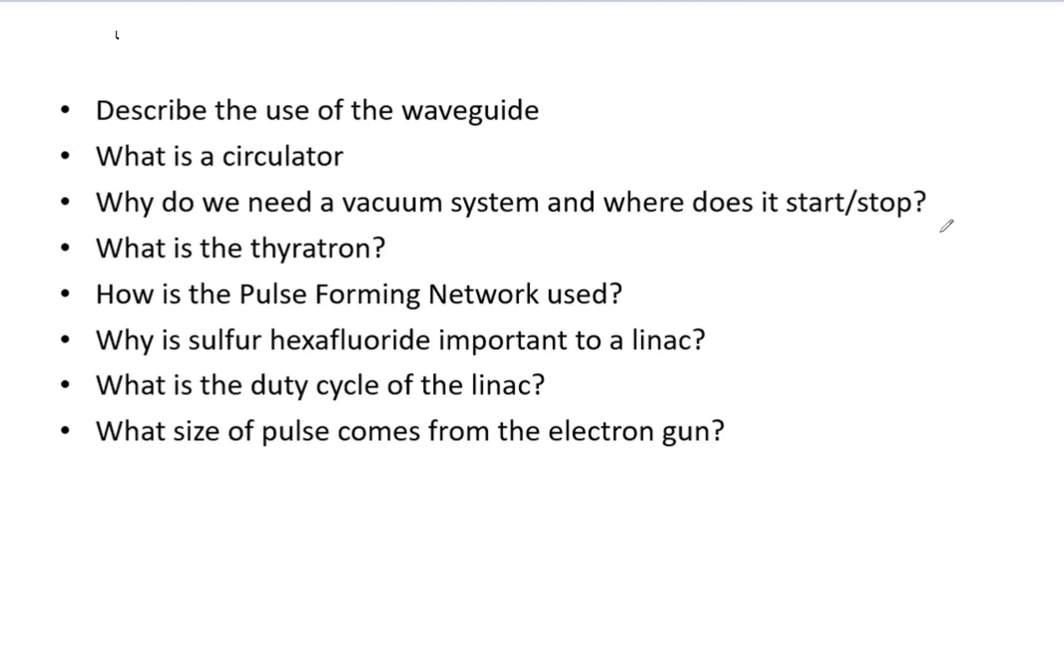So the klystron is under the vacuum, as is the electron gun assembly, as well as the accelerator waveguide, bending magnet, and target head, which uses a beryllium window allowing beam access into the beam shaping head. All those are under the vacuum. It's important because otherwise your electron gun would burn out and you would not receive any type of beam.